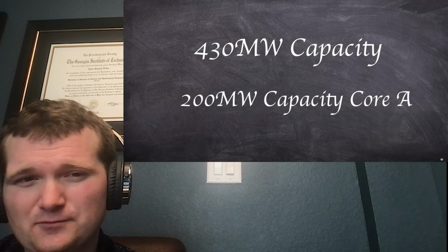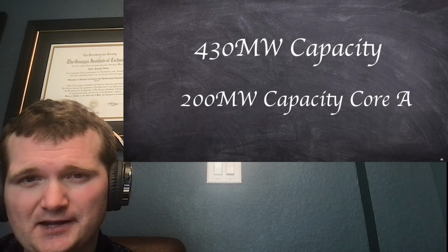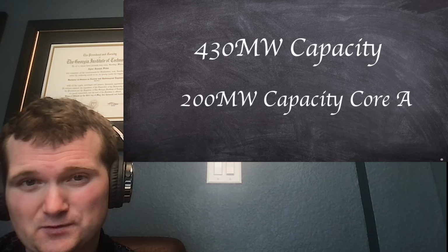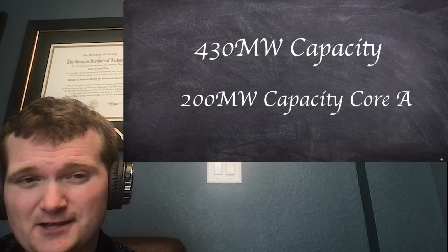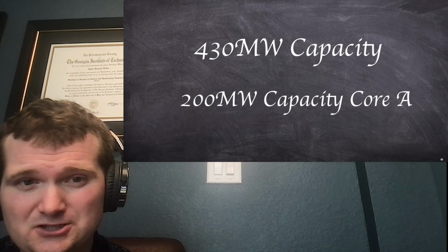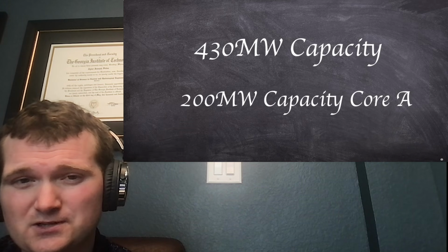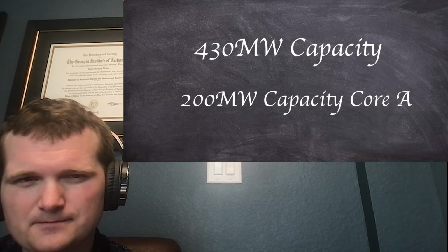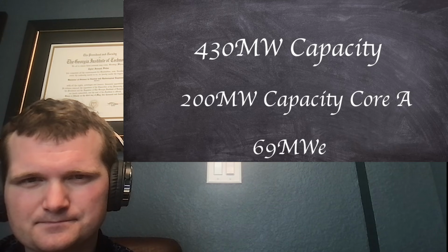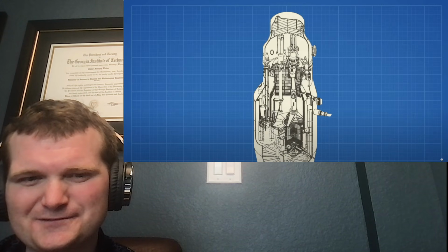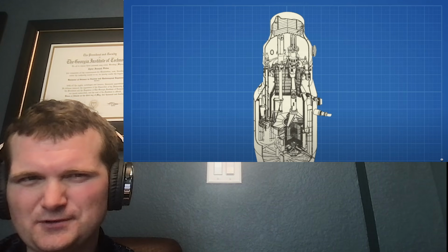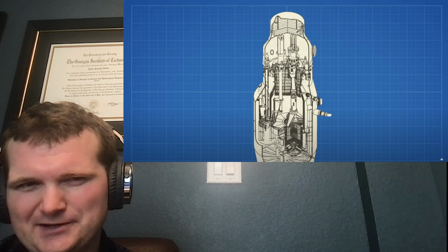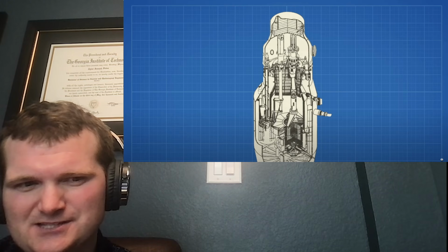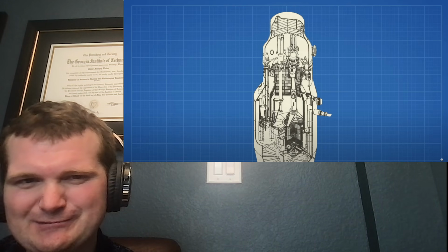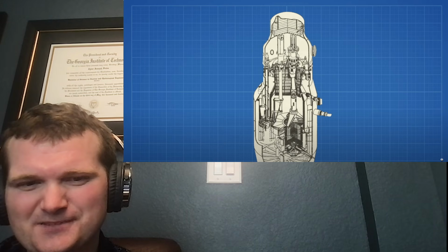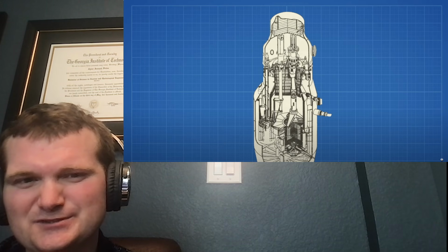The plant I worked at, which is one of the larger ones, had over 3,800 megawatts in the reactor. That's not to say you can't make something that big with a liquid sodium reactor, just this particular one, this is early stages of that technology. The reactor was capable of creating 69 megawatts of electrical power. That checks out. It's about a third of a typical steam cycle. Though this one, you would think you could do a little bit better just because you're running at a higher temperature, but you're ultimately limited by water and the pressure and the heat and pressure in your steam generator.